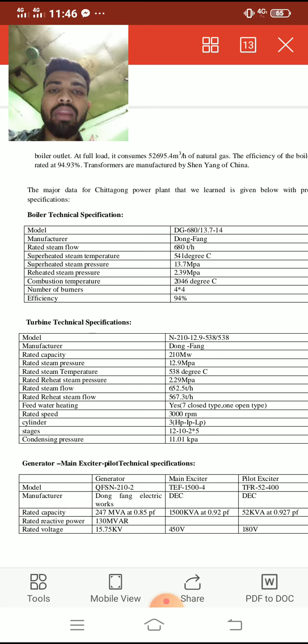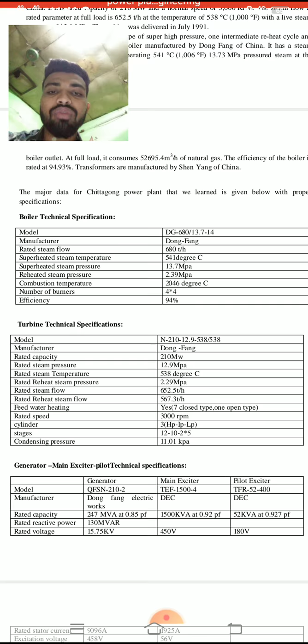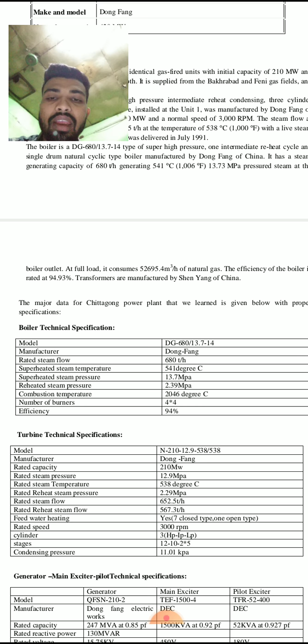Its generator main exciter, pilot exciter, and boiler technical specifications are most important. The major data for Chittagong power plant that we learned are given below with proper specification: number of burners 4x4, superheated steam temperature 541 degrees Celsius, and superheated steam pressure 13.7 MPa.